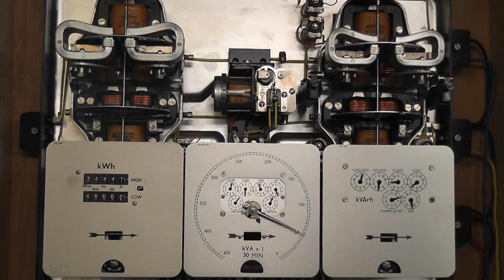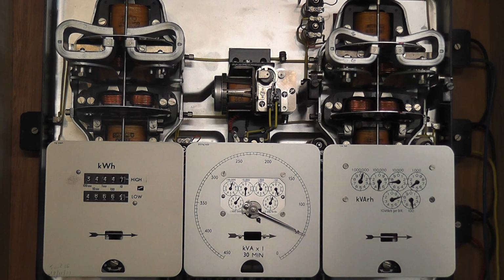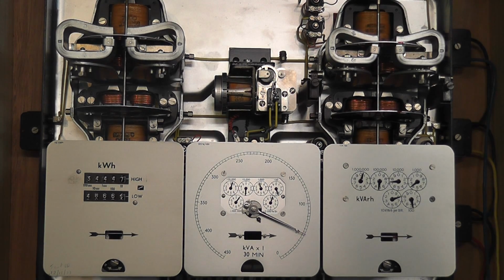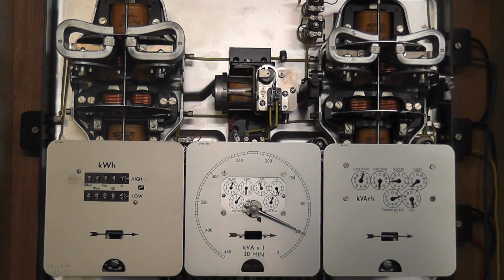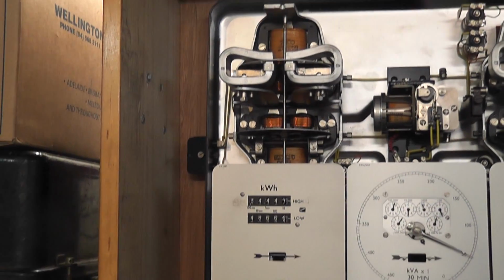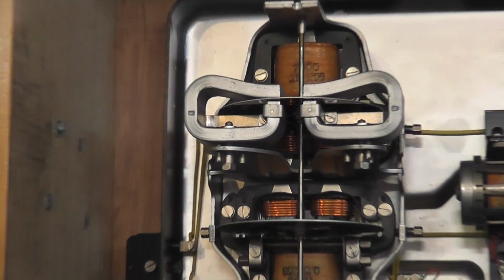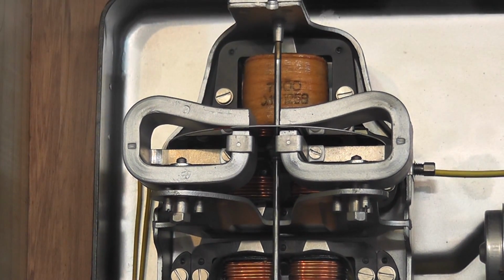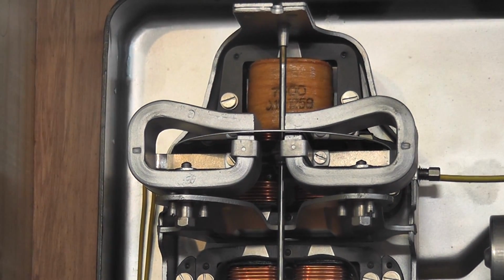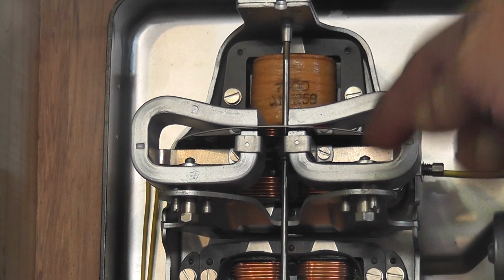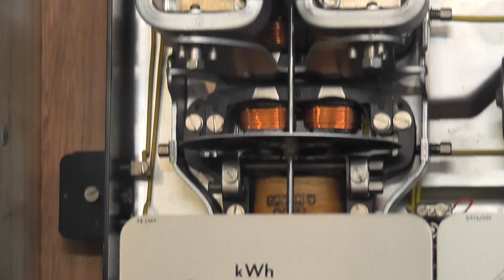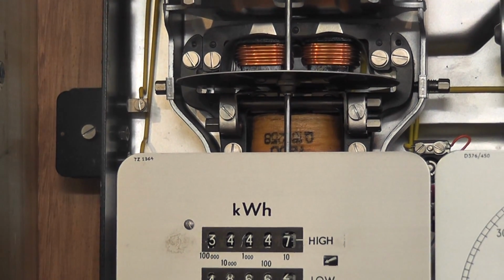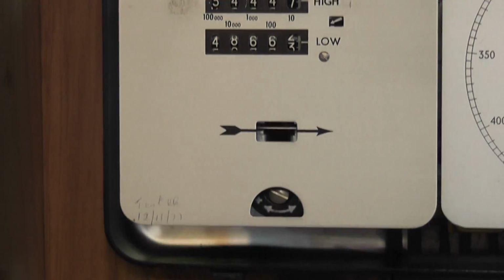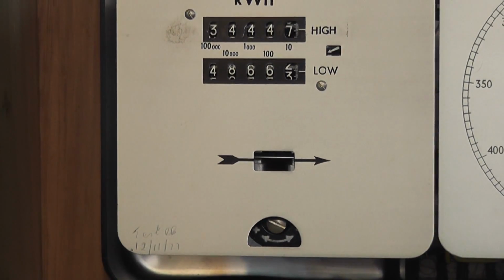These Landis Gyr Trivector meters are usually beautifully engineered, typical Swiss and English British engineering. Let's have a bit closer look inwards at the active component. Here we see the top brake magnets. Potential coil is up here, current coils, and then we got a potential coil for the middle phase, yellow phase, and there is another potential coil behind the nameplate.